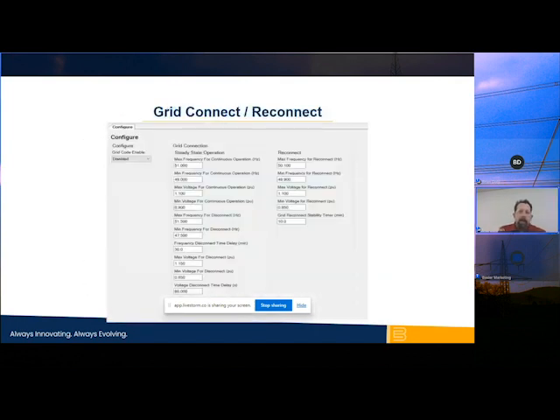But here's just a screenshot of how the voltage regulator is set up to do that. This is straight out of our BestComms Plus software for the DECS 250, I believe. It shows that it is defining those parameters that we just talked about. We're setting the limits: this is my max frequency for continuous operation, and my max and min voltage for continuous operation. And then I'm going to set those.